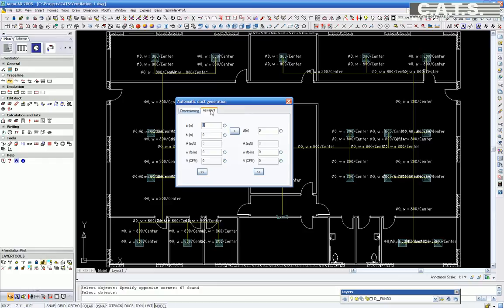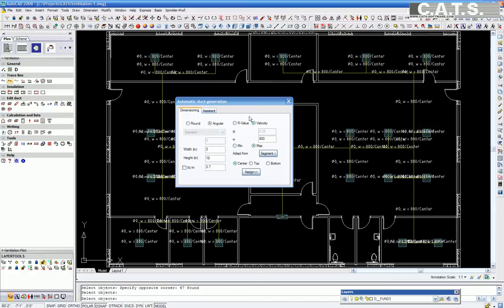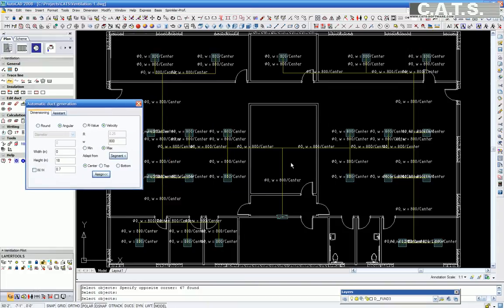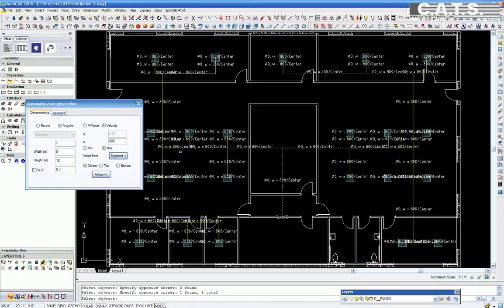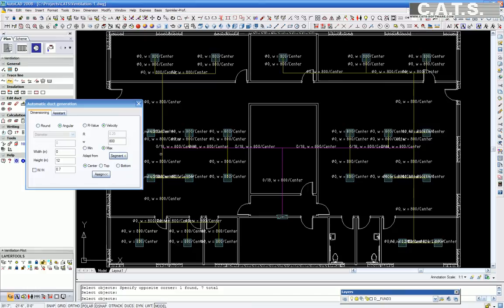We will now select the ducts to be converted from round to rectangular. The automatic duct generator window has a tab to the right which is labeled Assistant. This is nothing more than a duct calculator. We will assign our rectangular duct height. We will use the defaulted 18 inch dimension. In width, we will select zero. The software will calculate the duct width according to the velocity. We now select the lines to be changed to rectangular duct. They become purple in color.